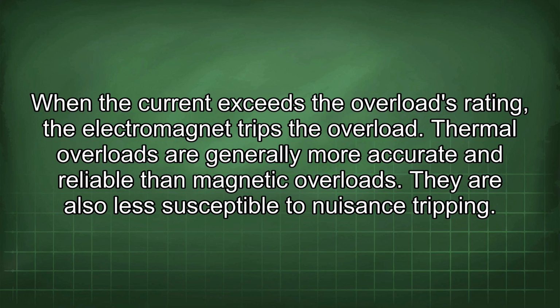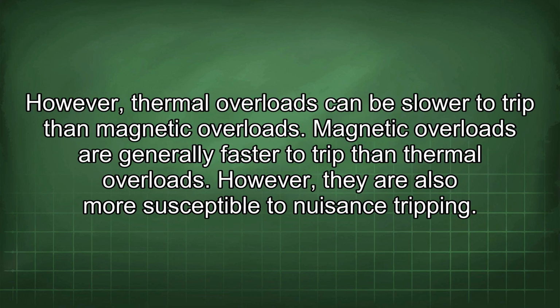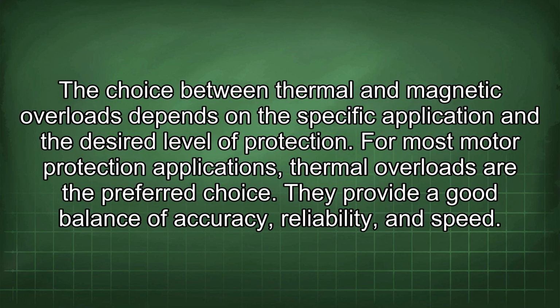Thermal overloads are generally more accurate and reliable than magnetic overloads. They are also less susceptible to nuisance tripping. However, thermal overloads can be slower to trip than magnetic overloads. Magnetic overloads are generally faster to trip than thermal overloads. However, they are also more susceptible to nuisance tripping. The choice between thermal and magnetic overloads depends on the specific application and the desired level of protection. For most motor protection applications, thermal overloads are the preferred choice. They provide a good balance of accuracy, reliability, and speed.